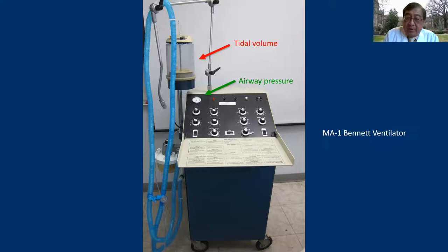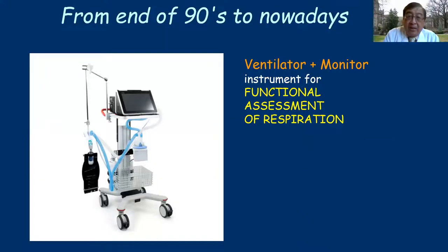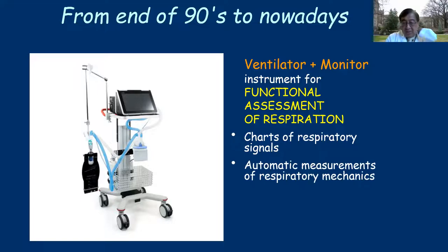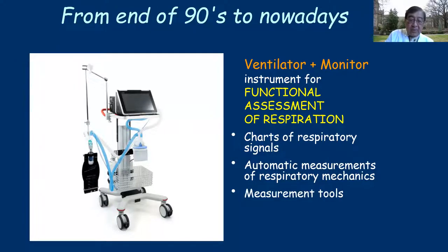By the way, the MA1 is still available on eBay, so it's pretty cheap these days. Nowadays, with modern ventilators, it's basically a ventilator plus monitor. Because of the computer, the ventilator can calculate and monitor many things — pressure, tidal volume, and all those things instantaneously. There are a huge number of different parameters on the modern ventilator, including automatic measurements. What's different from older ventilators is the much better screen interface and increased monitoring capability.